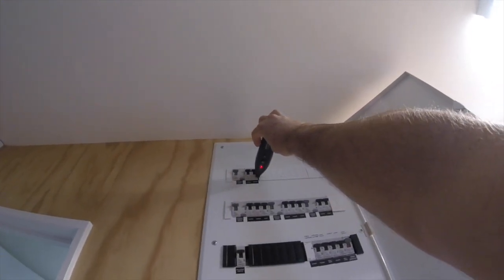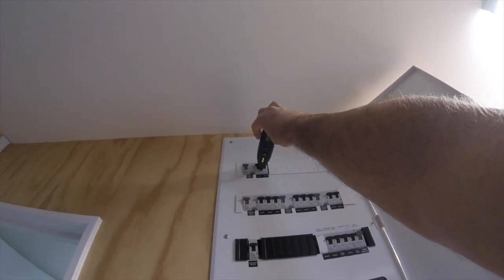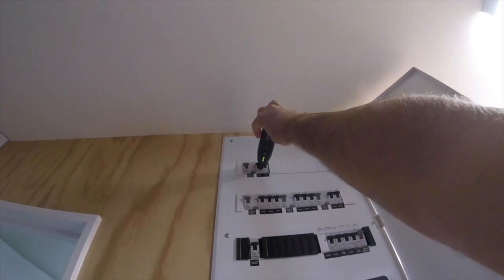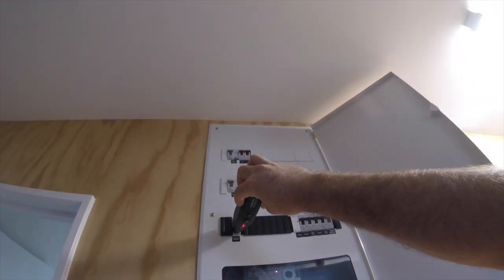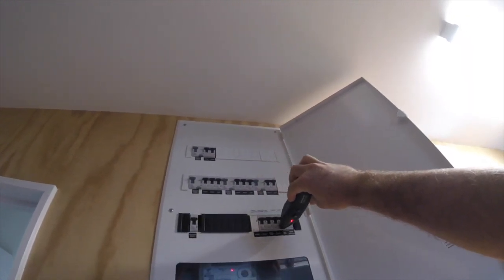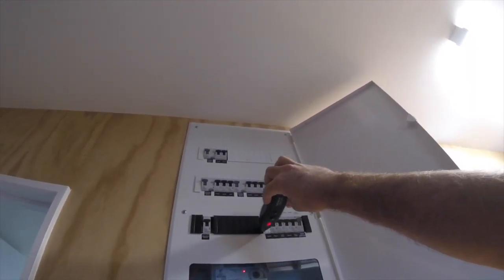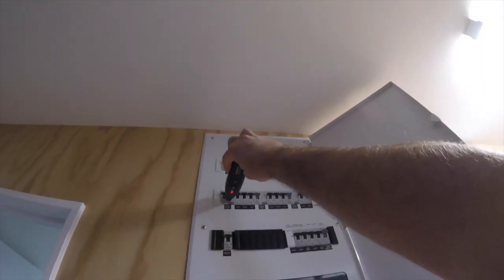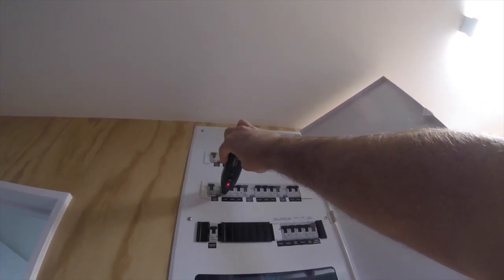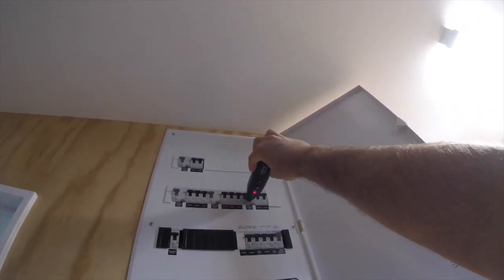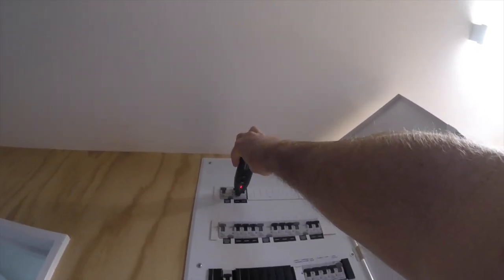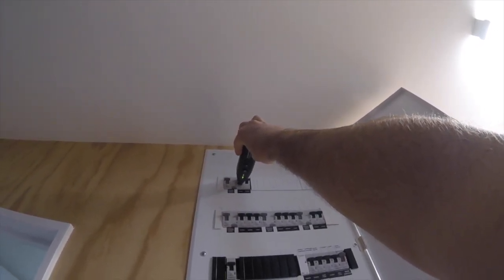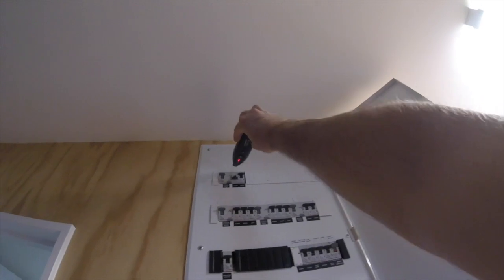There we go, it's just starting to pick it up now. And you'll notice now it's not picking up the main switch or anything else. And it's not picking up anything random. And it's missed, yeah, there we go, it's settled down and it's picked the right breaker. We'll flip that off.